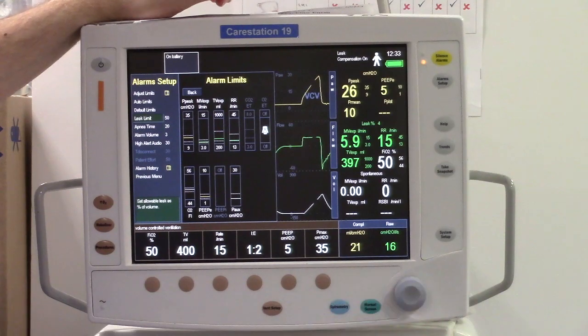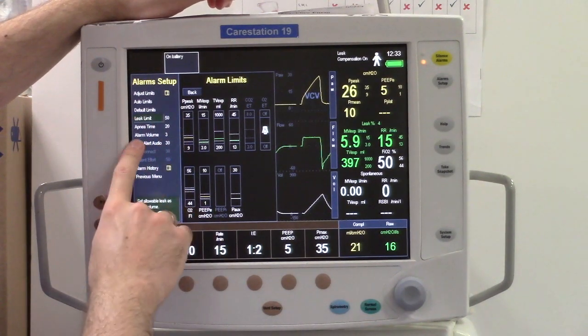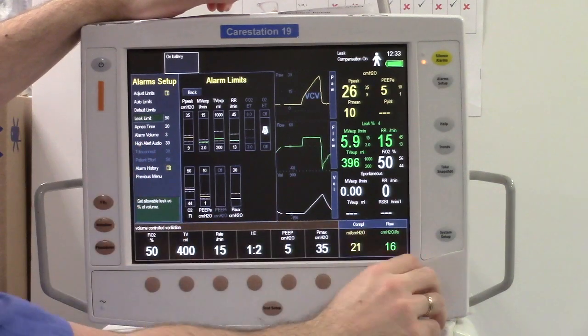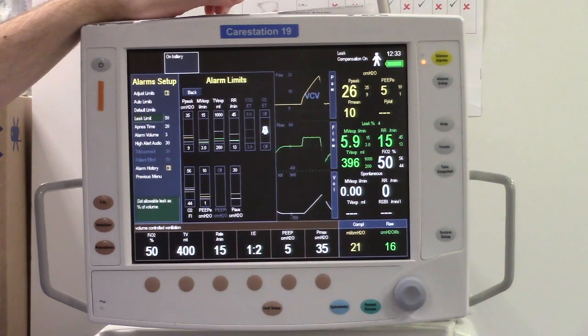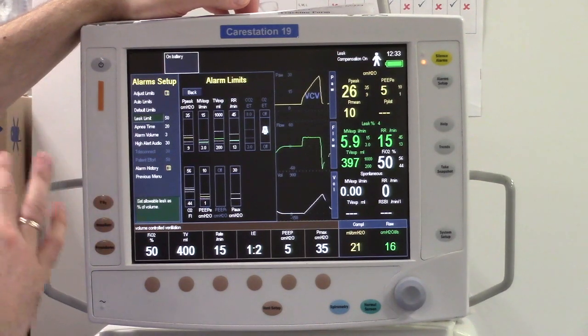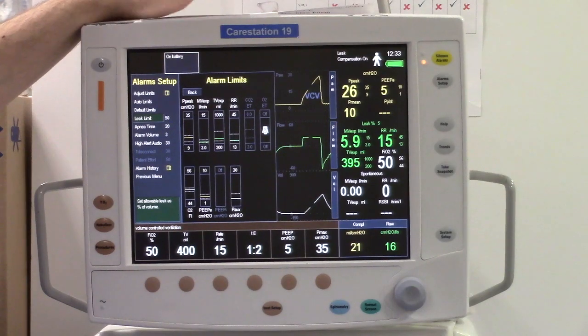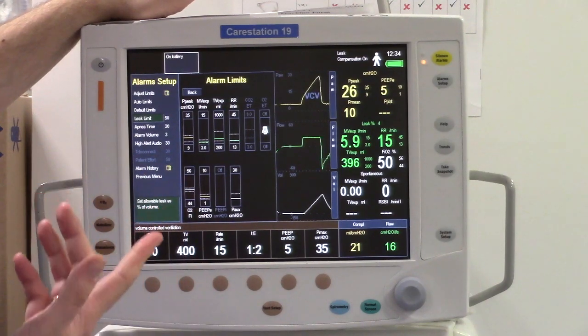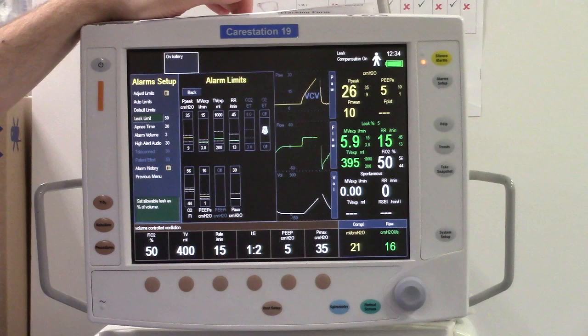Okay. Then you have other options here. Leak limit, apnea time, alarm volume. So leak limit, usually you may have some leak alarms which are related, obviously, to the leak. So on an intubated patient, you should not have any leaks unless they deflate the cuff. So if you know your cuff is up and you have leaks, then you need to pay attention to what's going on. It can be a leak from the circuit, it can be a leak from the tube, and so on. That's why it's important to set this alarm limit, yeah?